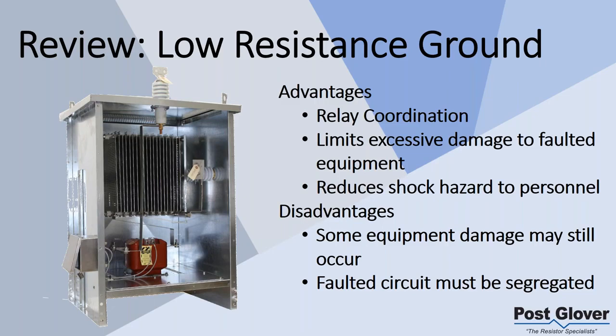Whichever one you accept, usually a low resistance ground system, because of the lower current, will allow you more time and therefore will help with that coordination while reducing the amount of damage. If you get below your damage curve, you can eliminate your damage, but sometimes you can't avoid that. Relatively, your damage is going to be much lower.